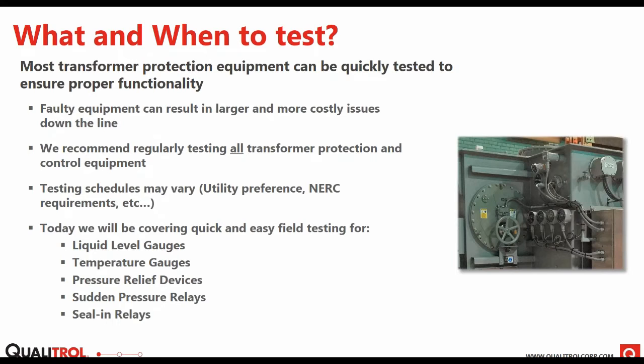So anything that you use to gather data and information from your transformer, we recommend to test that at some point. A lot of these, it's really not beneficial to set it and forget it. At some point during scheduled maintenance or any schedule that you may have, it would be wise to test a lot of this equipment. And testing schedules vary between utility to utility, location of that utility, NERC requirements, other IEEE requirements, and whatever preventative maintenance schedule that you may be on, it would be a good time to include some of these tests into that schedule. So today, we'll be covering quick and easy field testing for our liquid level gauges, temperature gauges, pressure relief devices, sudden pressure relays, and seal-in relays.